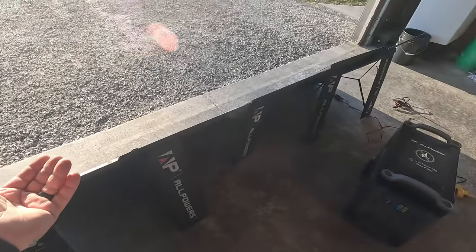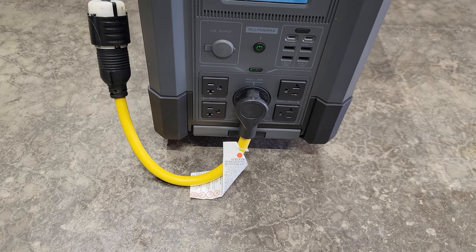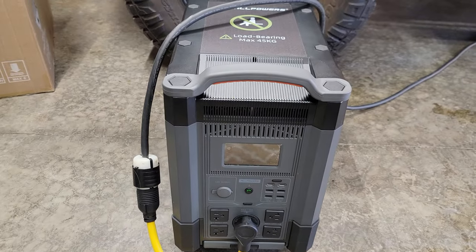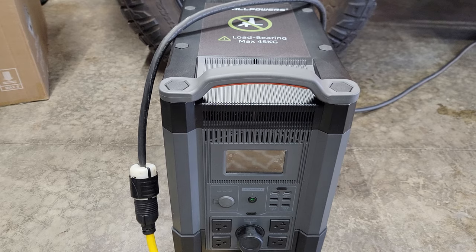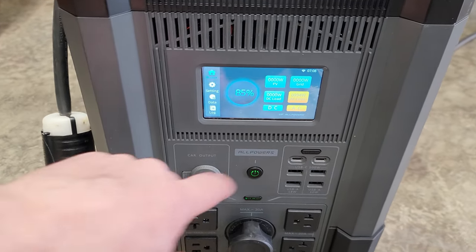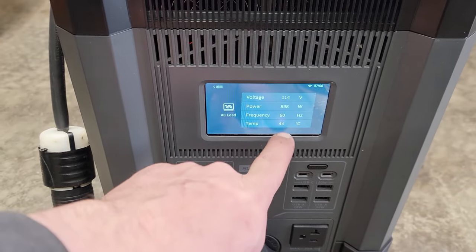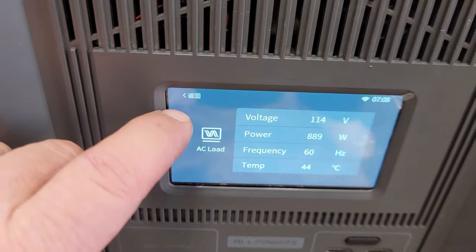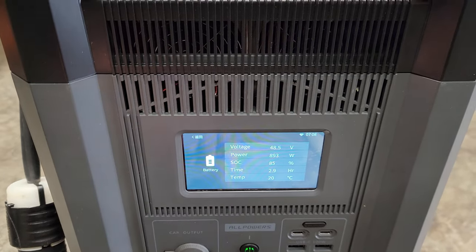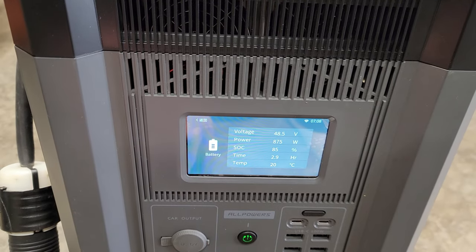I have it out in the garage hooked up to the house. This plug takes 120 volts 30 amp and splits it between both legs on the breaker panel — so you won't have 230 volts, as this unit does 3600 watts at 120 volts. We're powering the whole house currently at 893 watts, 60 Hz, at 114 volts; battery temperature is 44°C. Hitting the battery icon shows our battery voltage is 48.5 volts, power consumption is 875 watts, and we have 2.9 hours at the current rate. Battery temperature is 20°C.